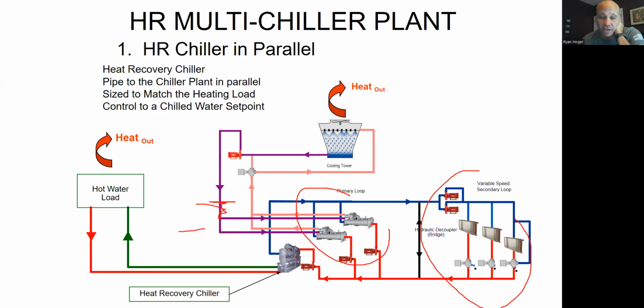I'm going to add this chiller on here, and I'm going to specifically have this chiller be different than these other two. This is going to be a heat recovery or heat reclaim chiller, a chiller that is specifically selected. It's the same components, evaporator, condenser, compressor, all that stuff, but it's specifically sized and selected to extract heat out of this loop and put it into that loop, right? So I'm going to use another refrigeration cycle to do that. So what's going to happen in this case, let's say this is wintertime. I can go ahead and shut my other machines off. I probably don't need a lot of cooling over here.